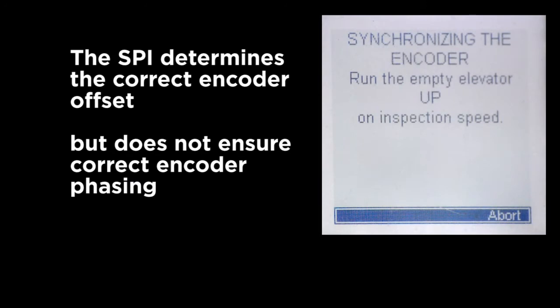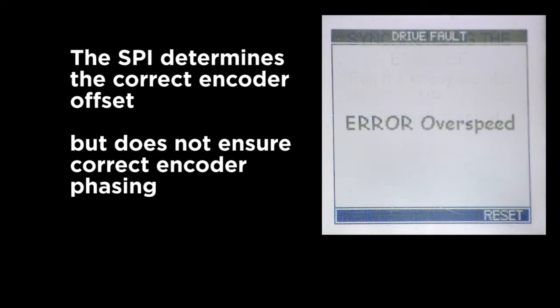The second step of this process is synchronizing the encoder. This checks whether the A and B phasing is correct on the encoder channels, and asks you to run the elevator in the up direction.